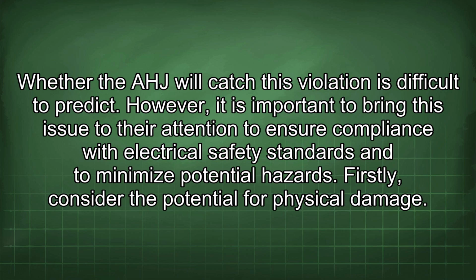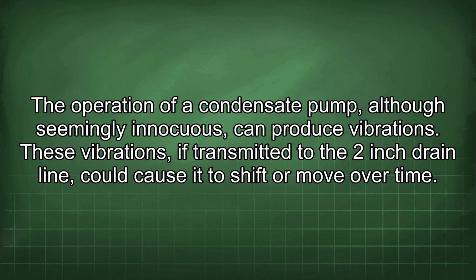Whether the AHJ will catch this violation is difficult to predict. However, it is important to bring this issue to their attention to ensure compliance with electrical safety standards and to minimize potential hazards. Firstly, consider the potential for physical damage. The operation of a condensate pump, although seemingly innocuous, can produce vibrations. These vibrations, if transmitted to the 2-inch drain line, could cause it to shift or move over time.